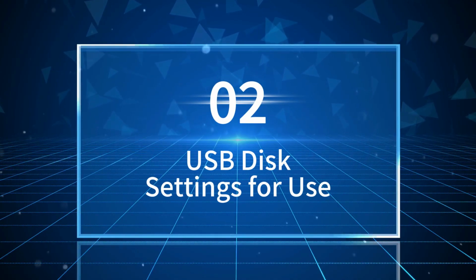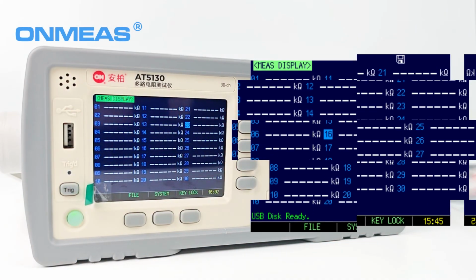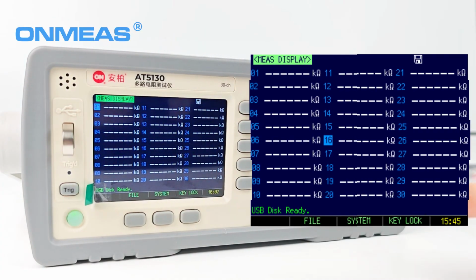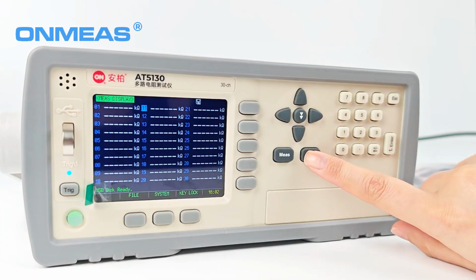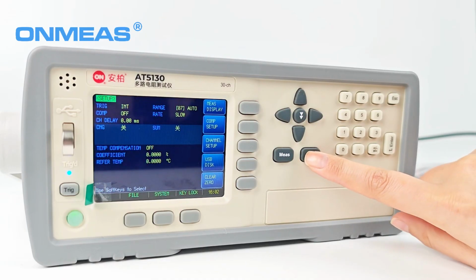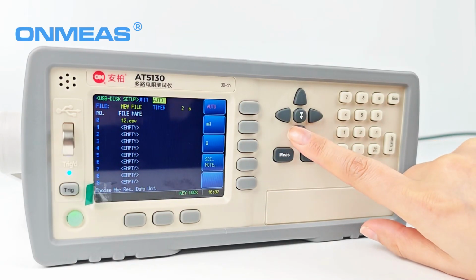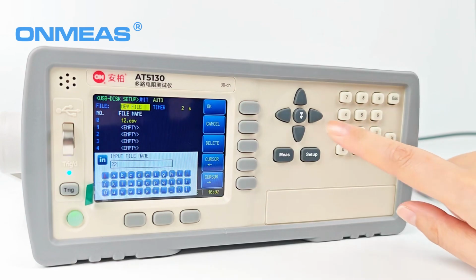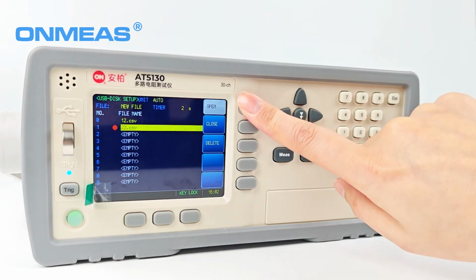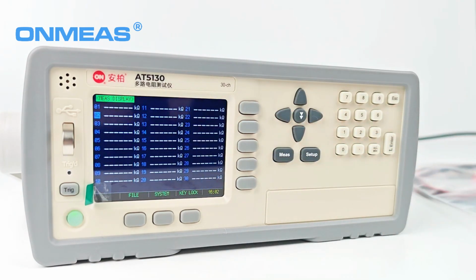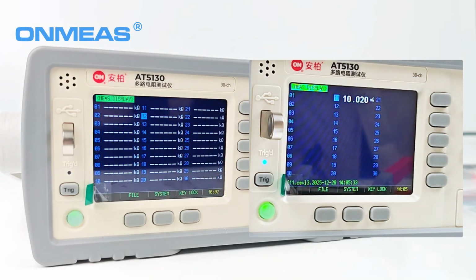USB flash drive usage. Insert the USB drive, and the screen will display USB disk ready. Enter the U-Disk settings page, select the unit as automatic, create a new file, set the time saving time, and then return to the measurement result display page. After the scanning is completed, you can see the file path and the saving time of the data file saved to the USB drive. Note that the actual saving intervals for the scanning channels when in single path mode and full open mode are different, and this is normal display.